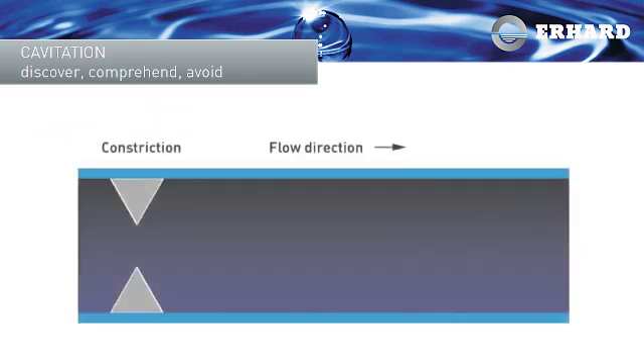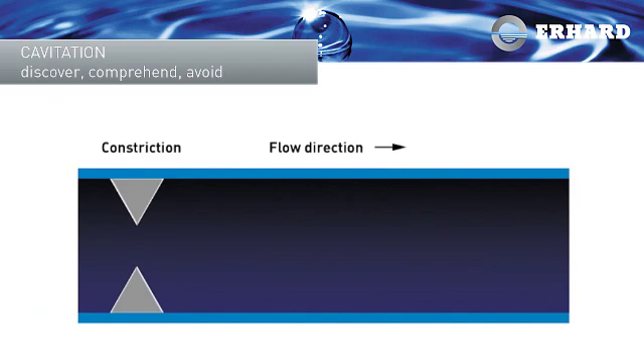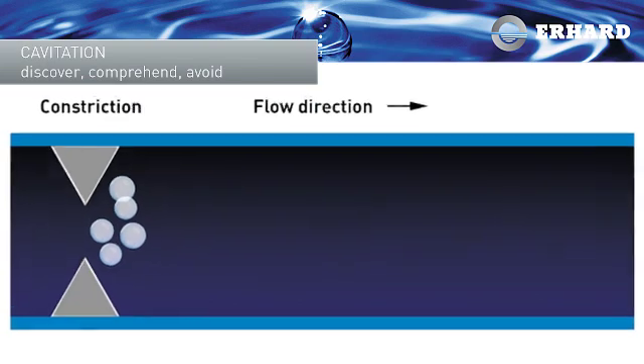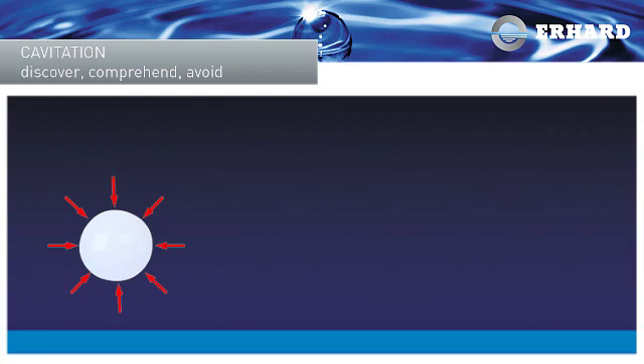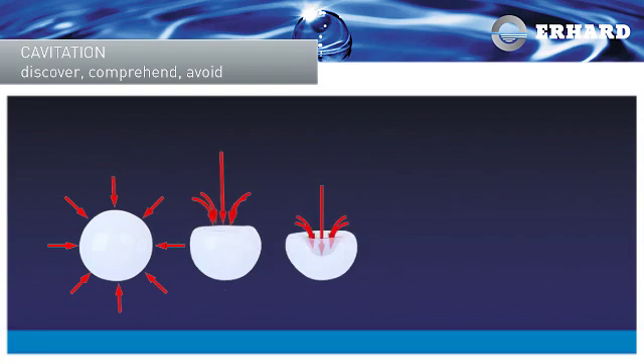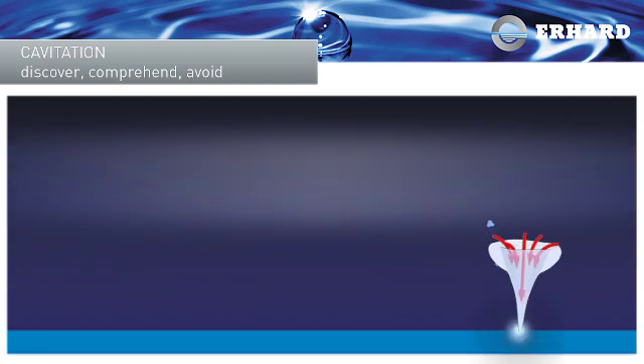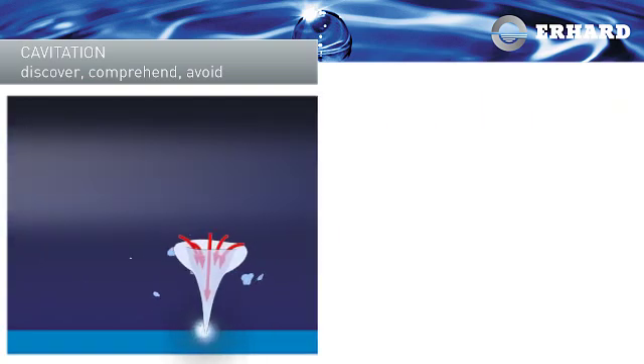In the case of cavitation, the vapour bubbles which form due to a pressure drop implode, recondensing to their liquid state when the pressure rises. The water surrounding the vapour bubbles is accelerated inwards within fractions of a second. Several of the resulting micro jets hit the body or pipe wall at very high speed, which causes pressure peaks up to 10,000 bar.